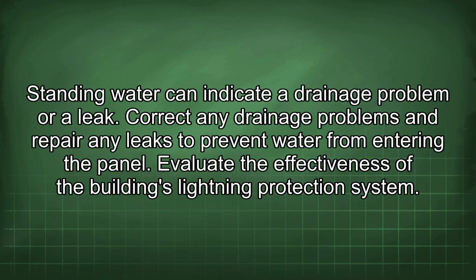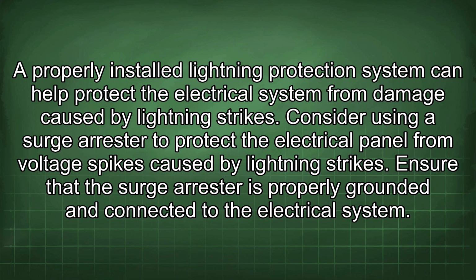Evaluate the effectiveness of the building's lightning protection system. A properly installed lightning protection system can help protect the electrical system from damage caused by lightning strikes. Consider using a surge arrestor to protect the electrical panel from voltage spikes caused by lightning strikes. Ensure that the surge arrestor is properly grounded and connected to the electrical system.